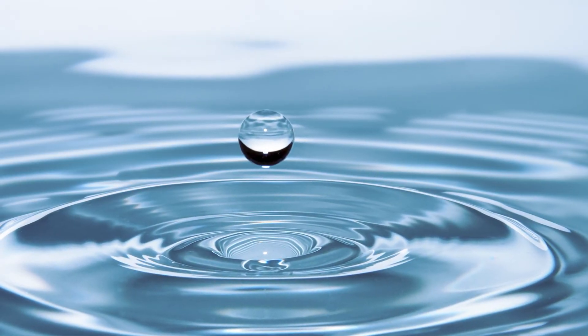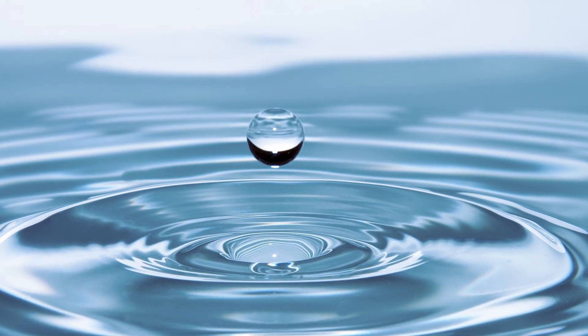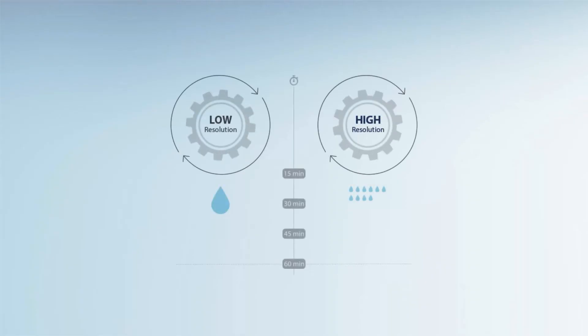A bolus is the amount of fluid that is pushed into the patient's tubing with each turn of the pump's motor. Pumps with lower resolution of flow push fewer numbers of larger boluses into the tubing to deliver the desired dose.